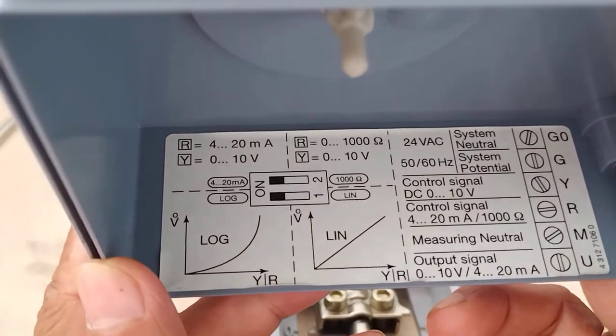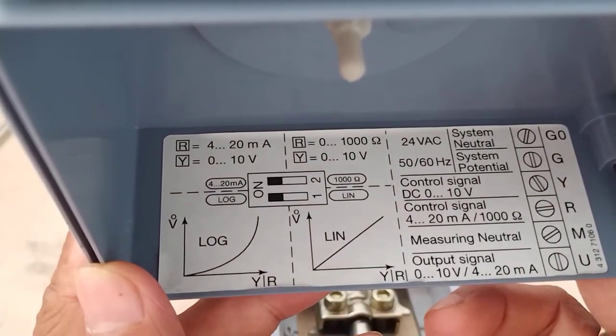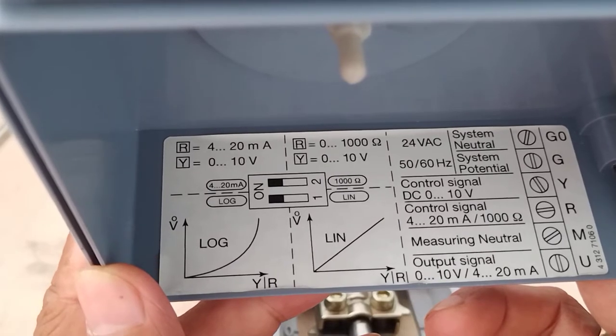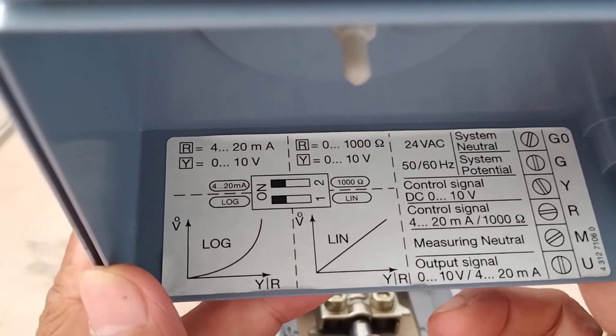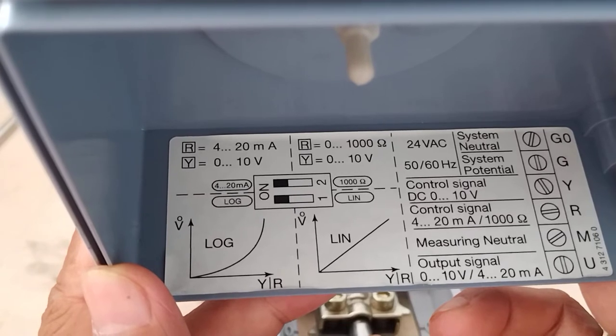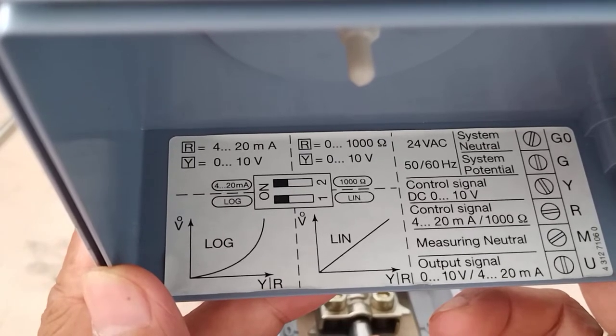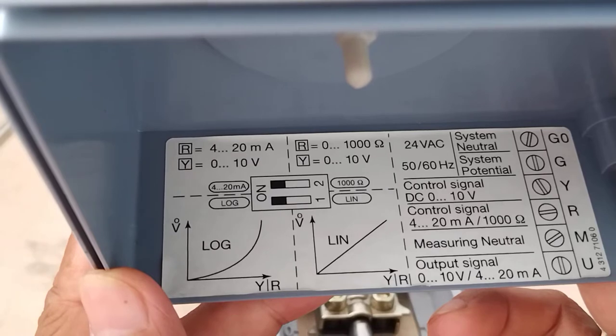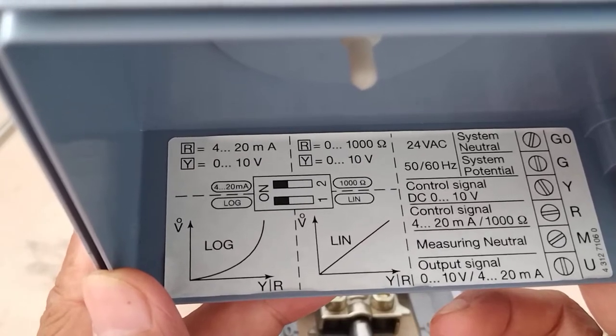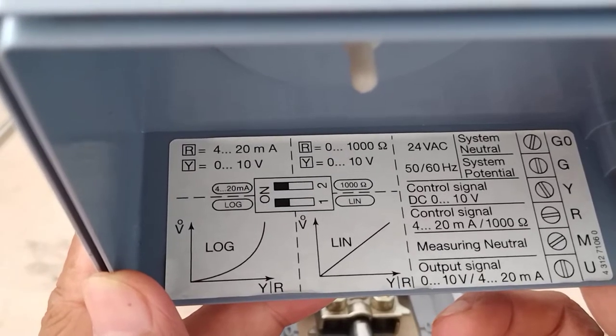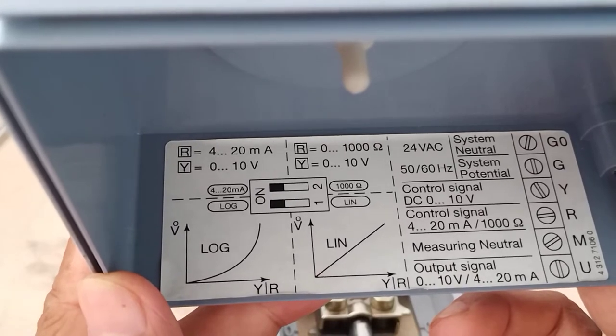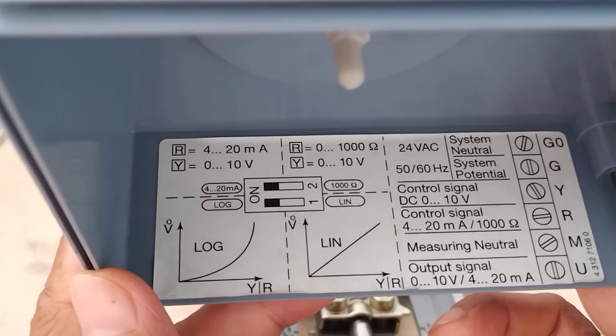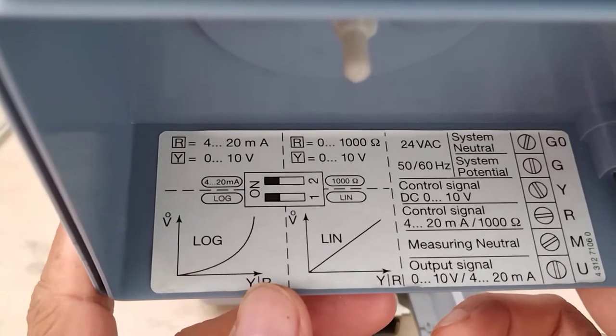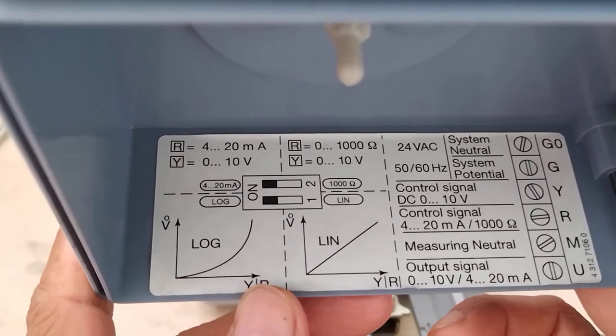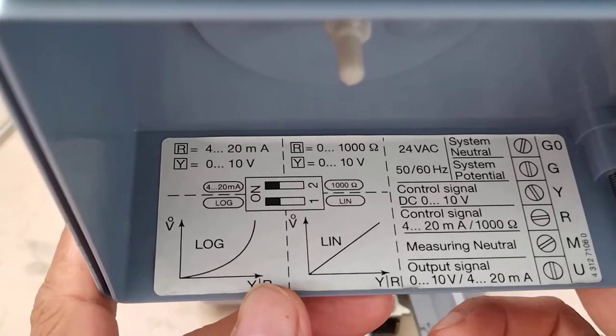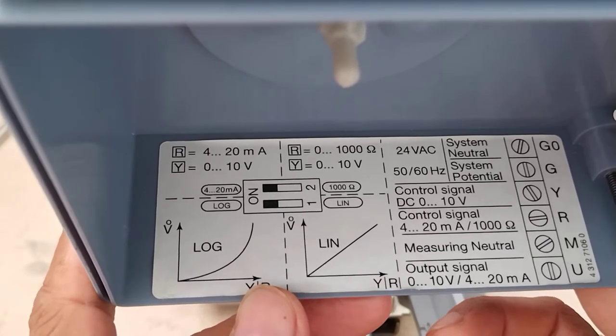Now, R and Y: R is 4 to 20 milliamps, Y is 0 to 10 volts. That is our control signal. So we can give 0 to 10 volts DC to open and close the valve, meaning 0 volts corresponds to the closed position, and 10 volts corresponds to 100% opening of the valve.